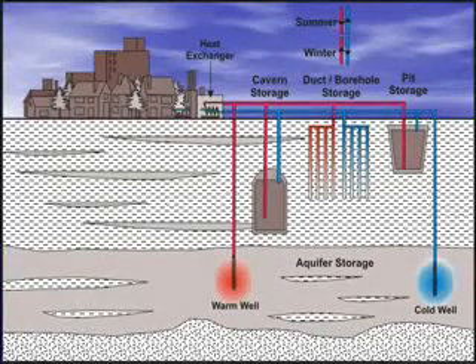If we look at the different types of underground thermal energy storage systems that exist, here's our buildings up here. If we have an aquifer underneath our building, we could potentially drill a couple of wells into the aquifer, and use one for pumping during one season, pull the water out, put it through a heat exchanger in the building, and then bring the water back and put it back into the aquifer.